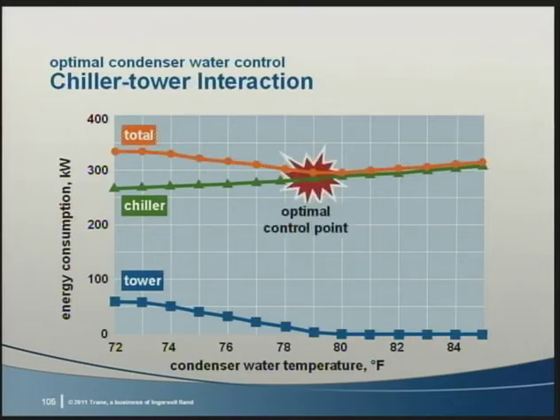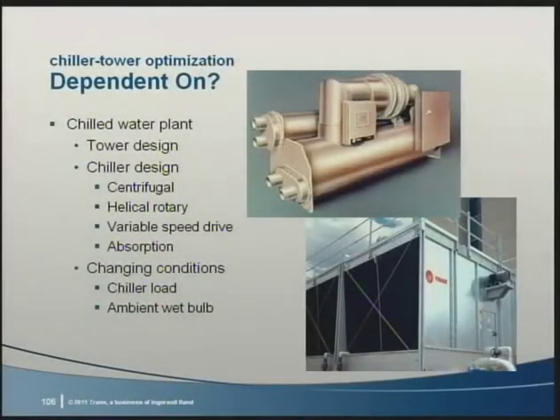is minimized at each point in time. For a given chiller plant, it's a function of chiller load and outdoor air wet bulb. So, how is this optimal temperature calculated? For a given chiller plant, we first define what are the design parameters of the cooling tower. Also, the chiller design parameters and the chiller type.